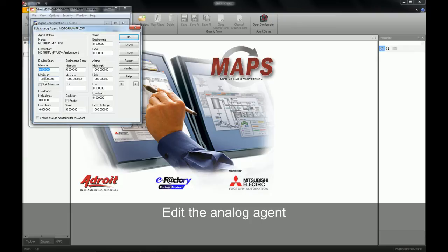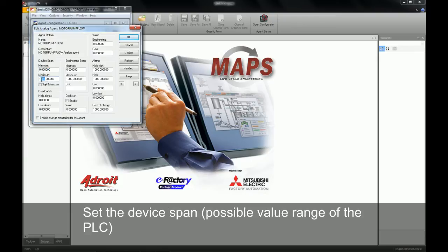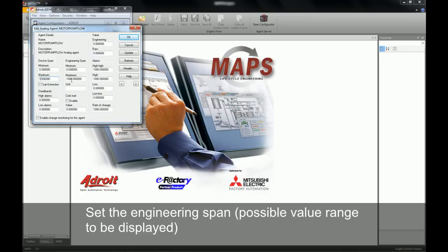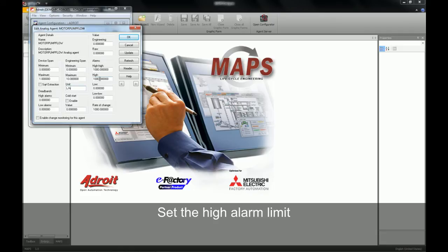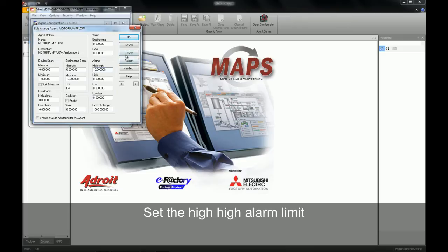We will be adjusting the device span of our analog agent — this is the span in the PLC. We can then specify an engineering span or range, which will be what we display to our operator. We're going to give our analog agent a unit value of liters per hour. We can then go and edit our alarm limits: our high alarm limit or first up alarm will be given a value of 8, and our high-high or second up alarm a value of 10. We hit the update button to accept all changes and click OK.